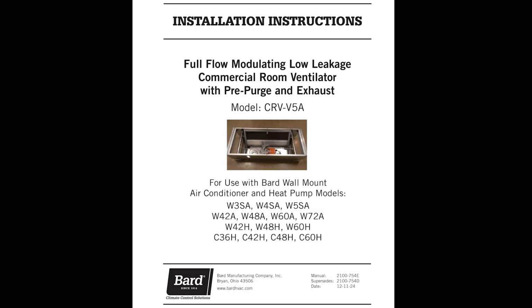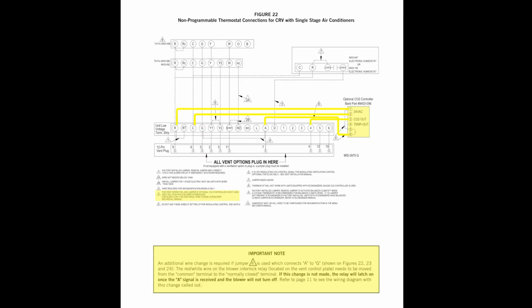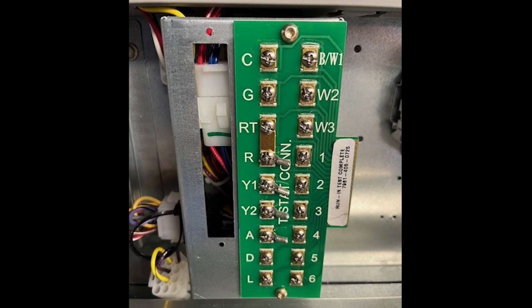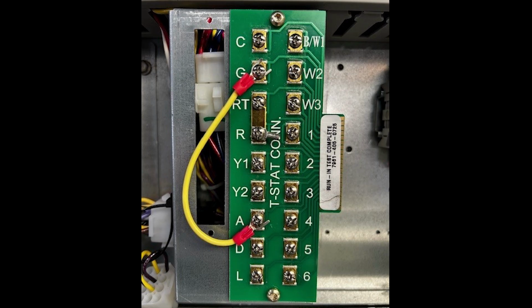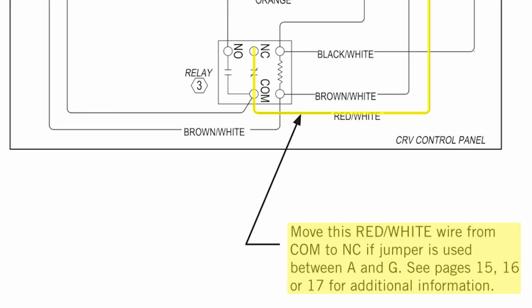This basic non-CO2 sensor control method has 2 choices also. Do you have a stat or EMS with a separate function to control ventilation independently of heating or cooling? If so, then energize terminal A on the low voltage terminal block. If you want the damper to open when G is energized, do not energize A on the low voltage terminal block. Instead, add a permanent jumper from G to A. And also move the red-white wire from the COM to NC on the separate blower interlock relay next to the control board in the electrical panel.